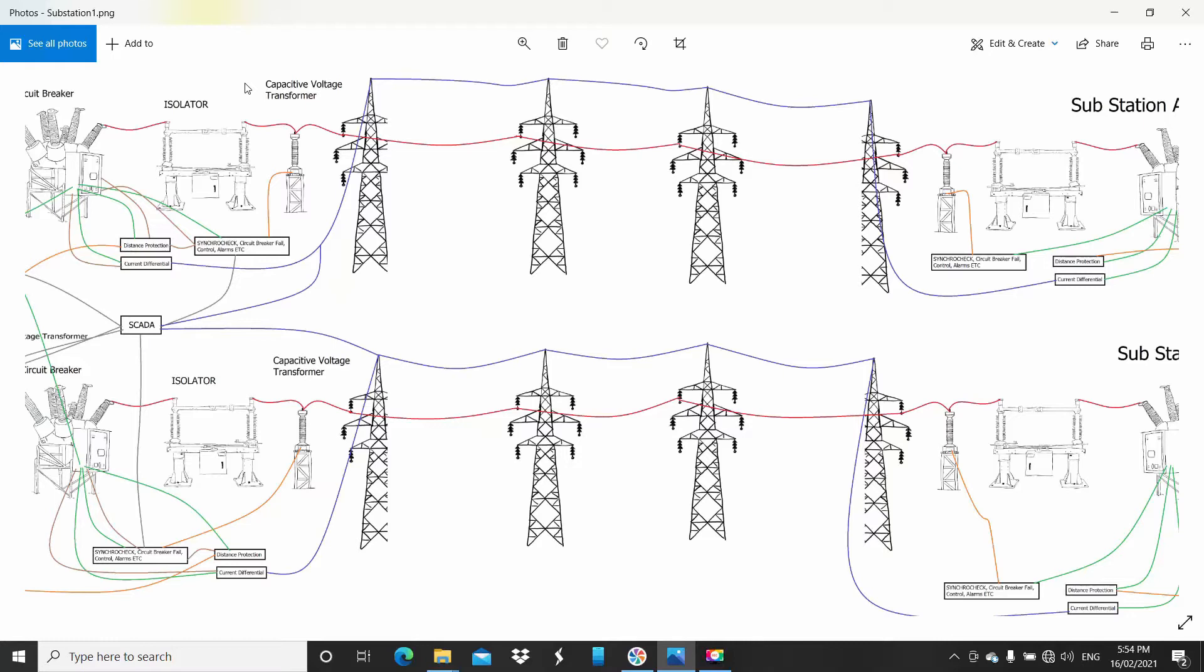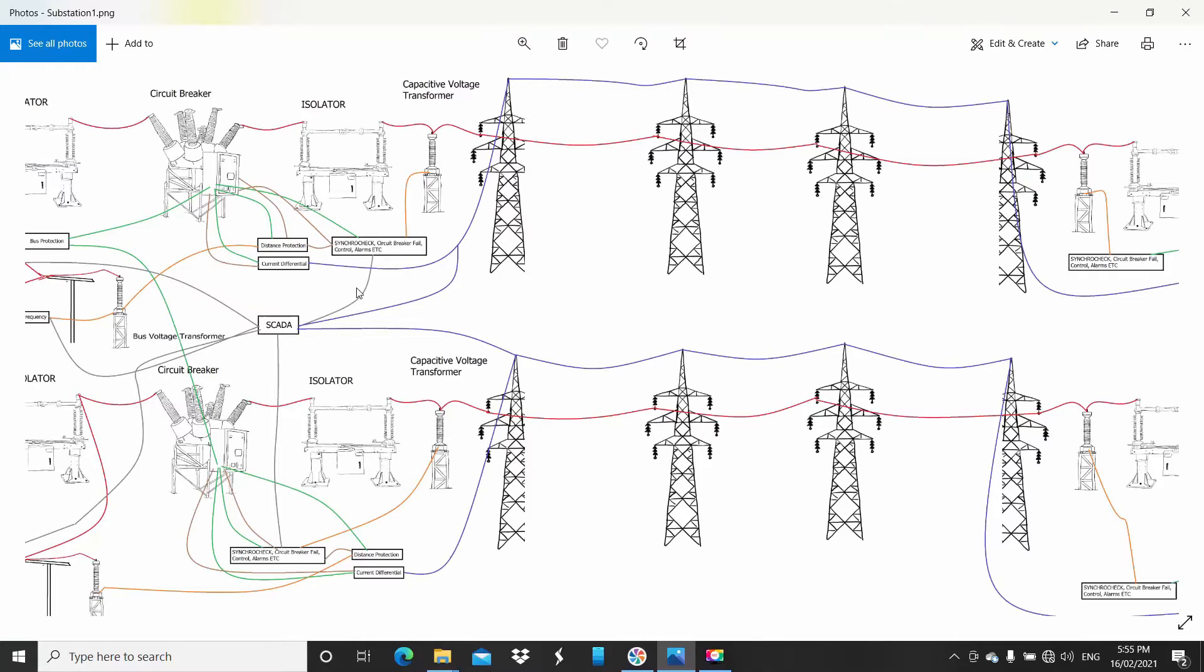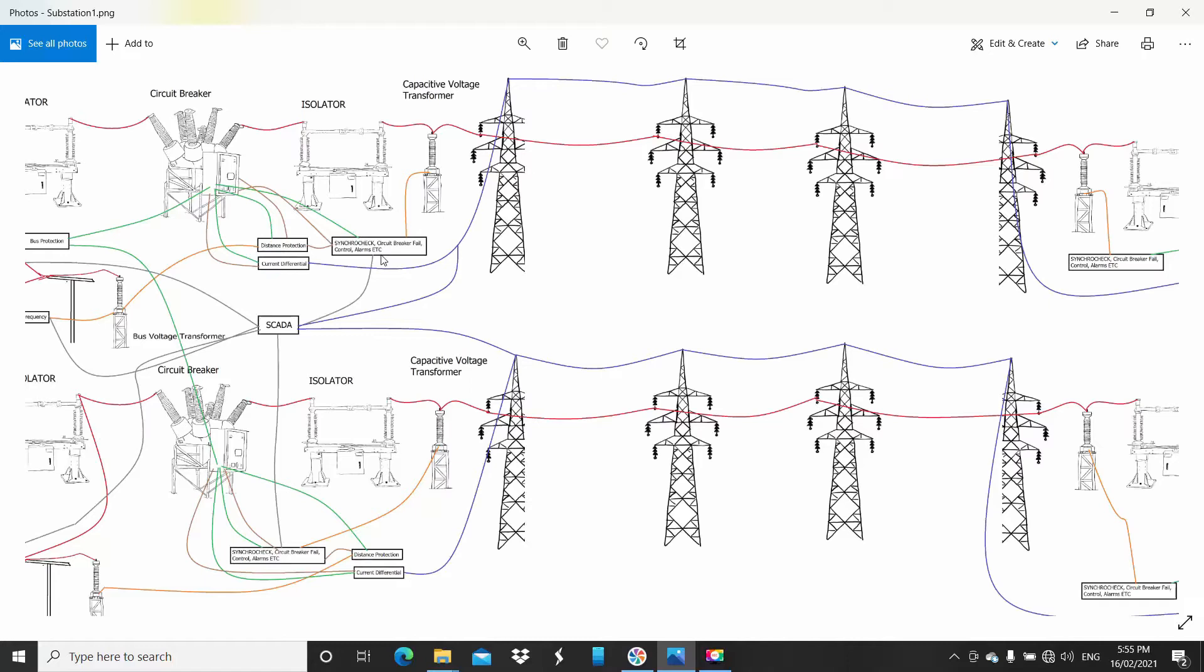I have three different types of relays on this transmission line. I've got a synchro-check, circuit breaker fail control, alarms, trip, close relay—that's called a circuit breaker management relay. So synchronization is when you have a very long line and you've got a voltage source on one end of the line and one on this end of the line, what you can find is they're at a different frequency or not much of a different frequency.